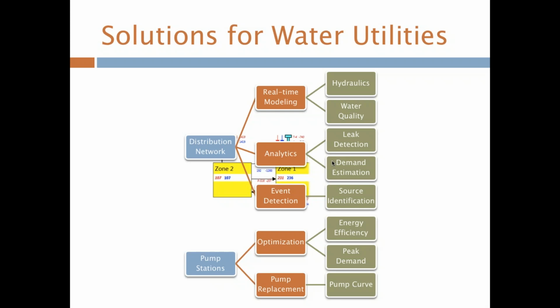For example, if you have the flow rates out of your pumping stations and then you also have level transducers on your tanks, then you can translate the tank level fluctuations into the demands of the tank. And there is some advanced analytics that gets applied before we can easily convert the tank demand fluctuations into demands, because the tank levels are noisy. And so you can apply some very interesting mathematical techniques to get the smooth demands from the tanks.